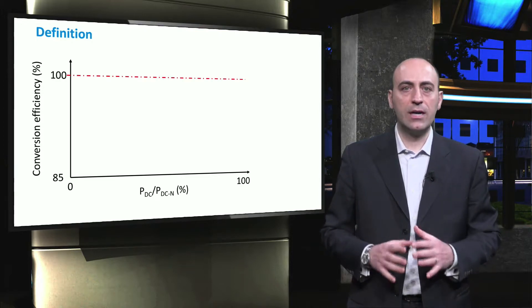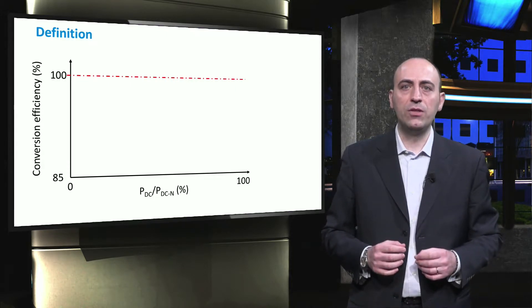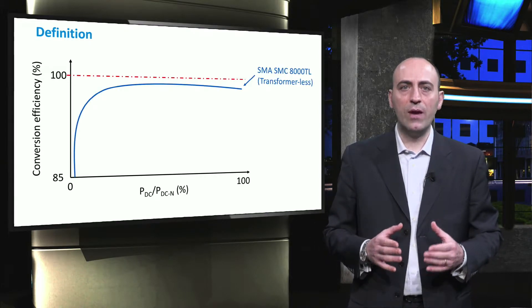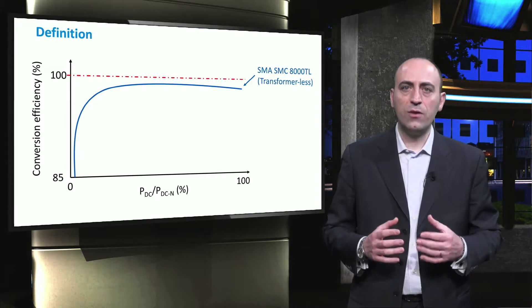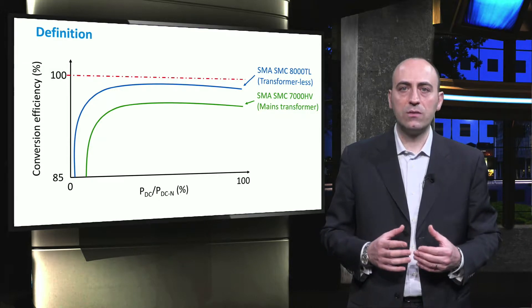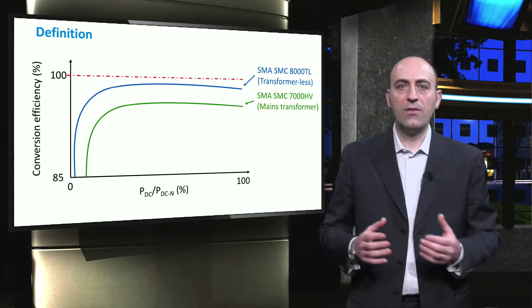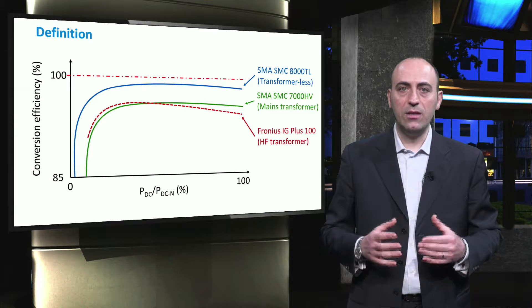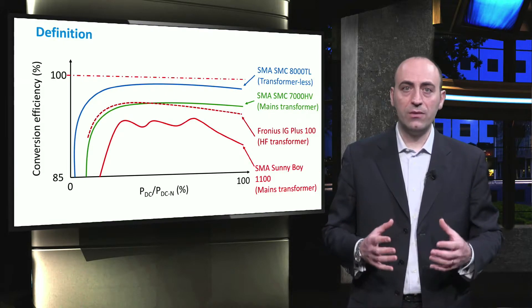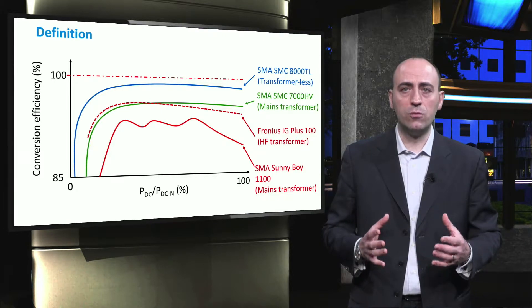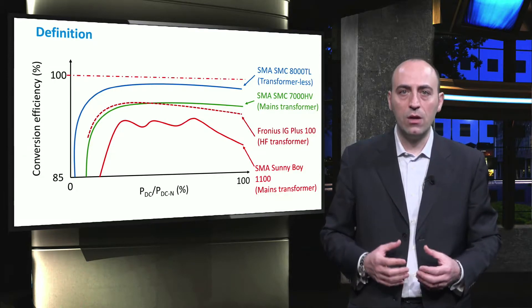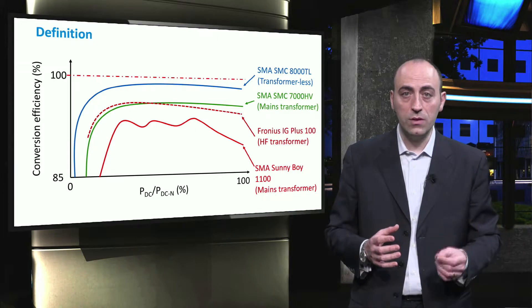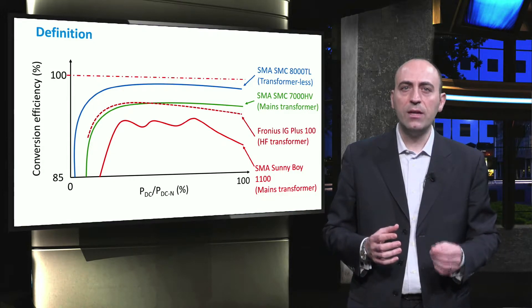Given that an inverter cannot be 100% efficient, a typical shape of the efficiency graph is the one shown in the slide. In this case, the behavior is referred to a transformer-less type of inverter. Different efficiencies can be found for different types and models of inverters, such as one with the mains transformer and the high-frequency transformer. It should be noted that every inverter and every manufacturer show a different behavior when it comes to efficiencies. This variety of patterns suggests that it is almost impossible to provide an analytical and unified model for the inverter efficiency. This explains why the inverter efficiency as a function of the input DC power for various DC voltage levels is usually given in the datasheet.